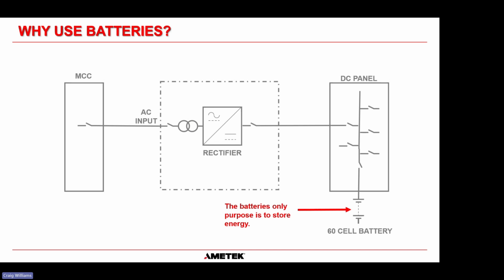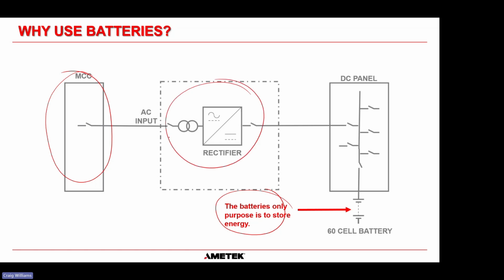So why do we use batteries? Well, hopefully you know this anyway, but the battery's only purpose is to store energy. Usually you have 480 volts coming in from your MCC, going into a rectifier charger circuit here that converts the AC into DC here. And then the DC goes onto this bus and keeps the batteries charged. And then you connect your DC loads through this DC panel. And it's only when the MCC fails, if we have a power outage, that the batteries say, okay, I'm available to do whatever you need me to do, whether it's trip, close, do whatever you need to do on the switchgear system.